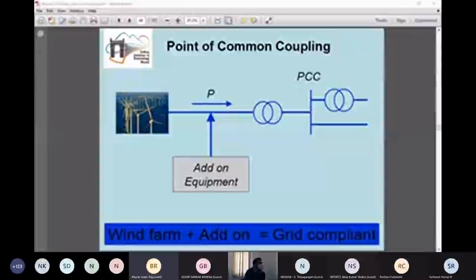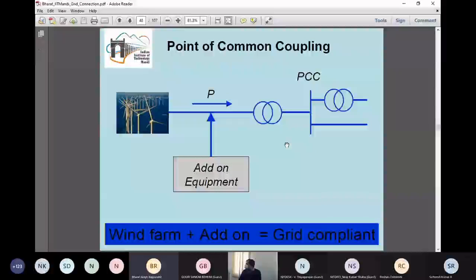One possibility is that every technology, wind farm or solar farm, is augmented by itself so that it is able to meet all such grid connection requirements that we have discussed. The next possibility is to have additional equipment like a static compensator, SVC, diesel generator set, energy storage or whatever, added to this wind farm or solar farm so that the overall grid connection requirements can be met at the point of common coupling.